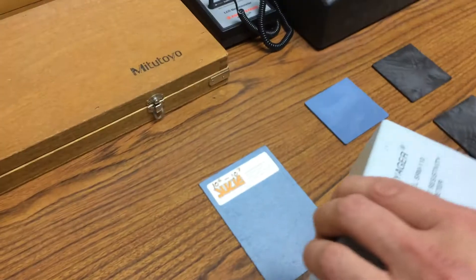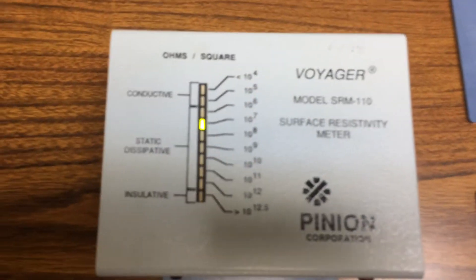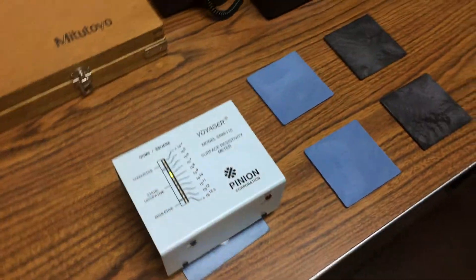We'll first go to a plaque that we use for calibration. It consistently reads in the 10⁶ to 10⁷ range.